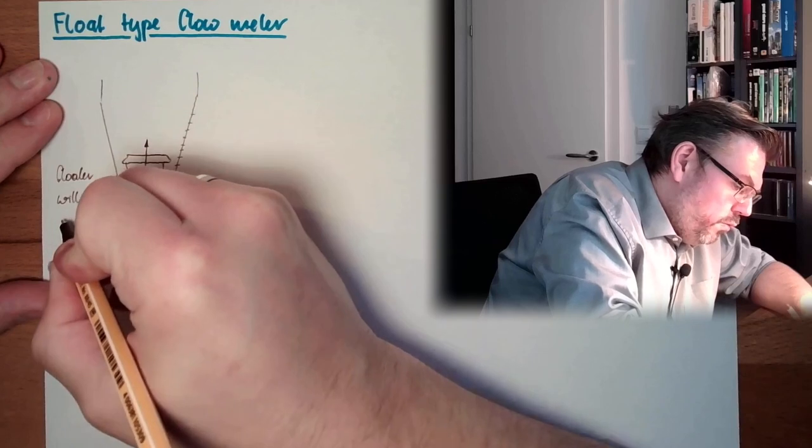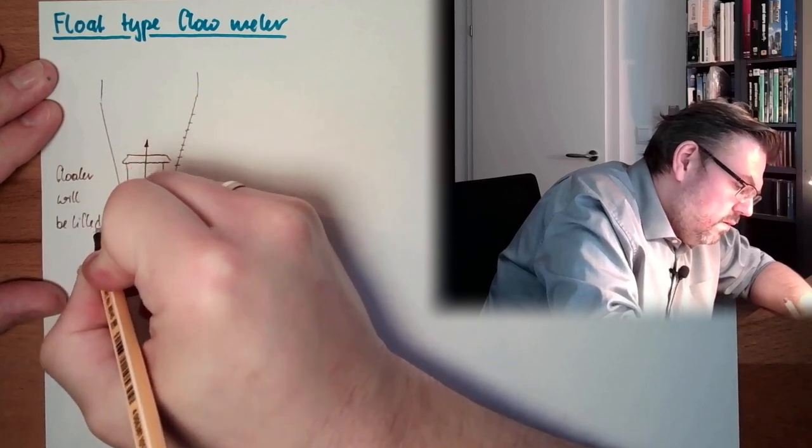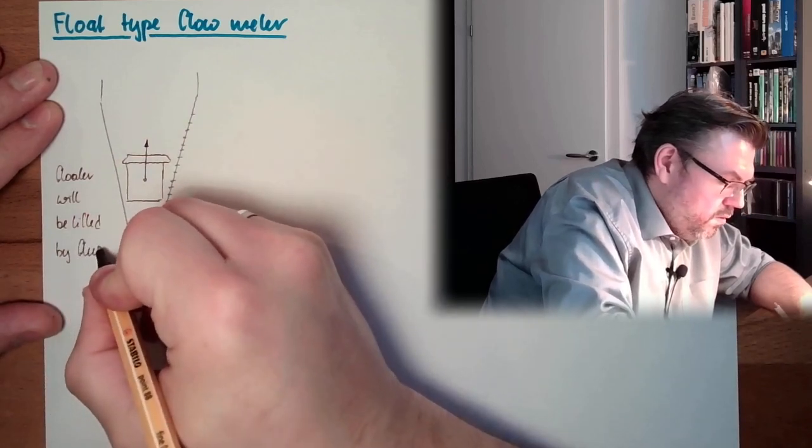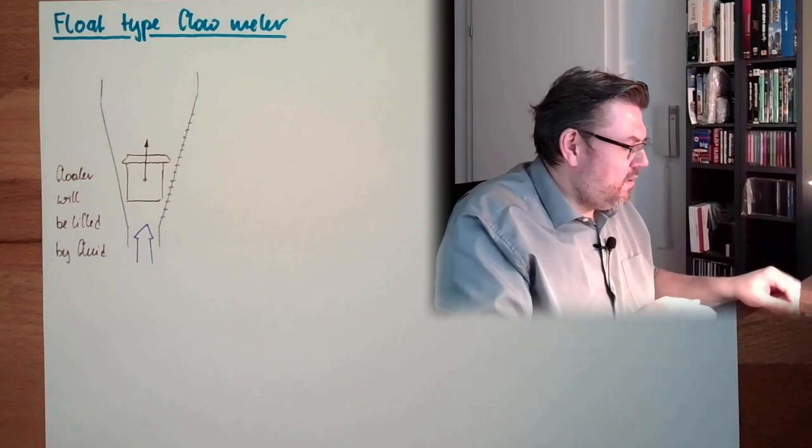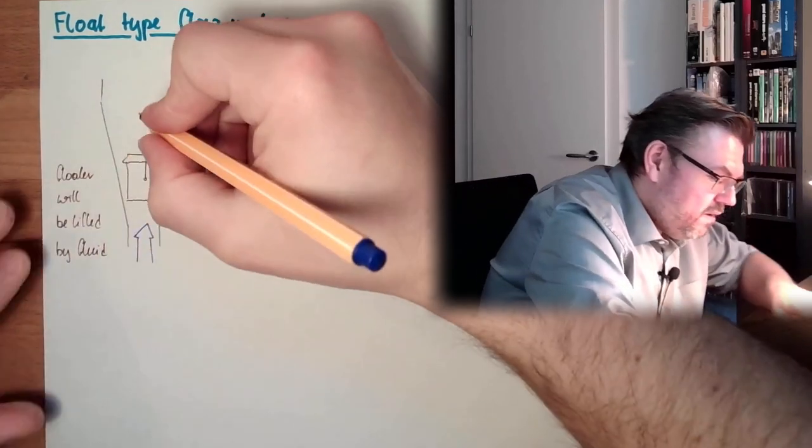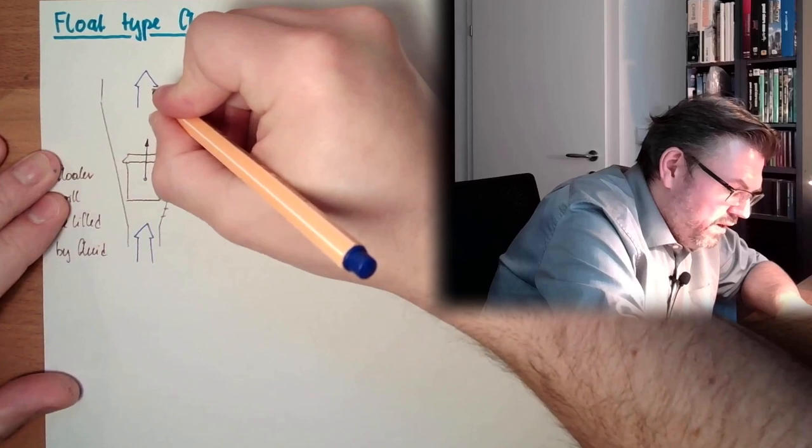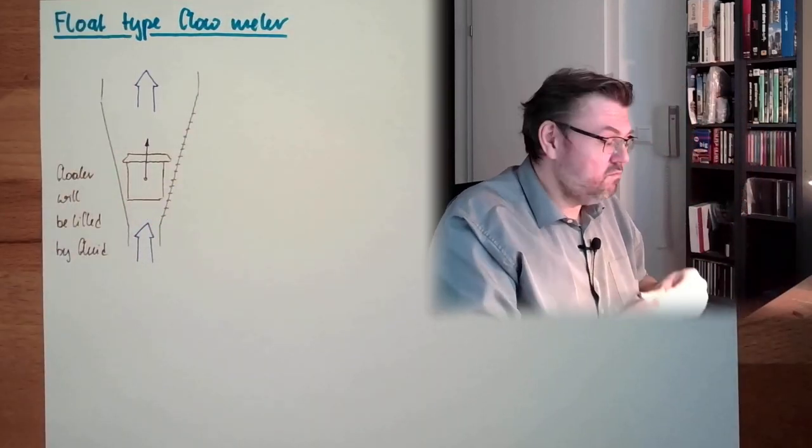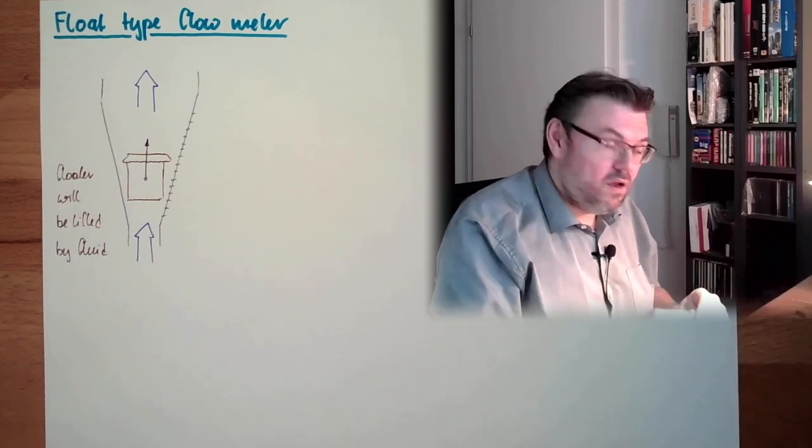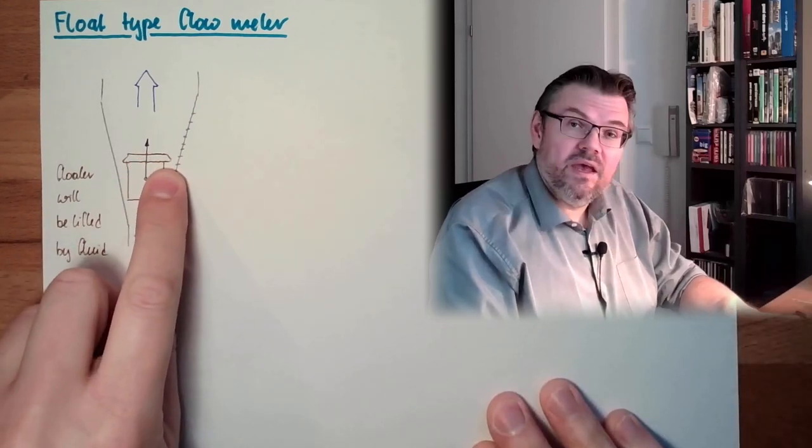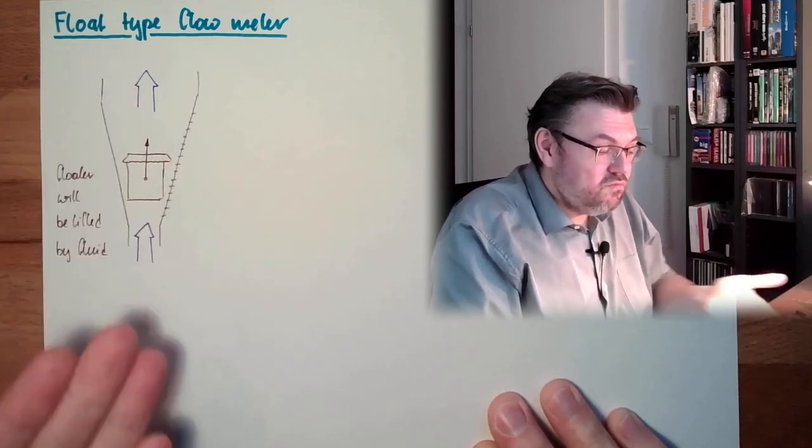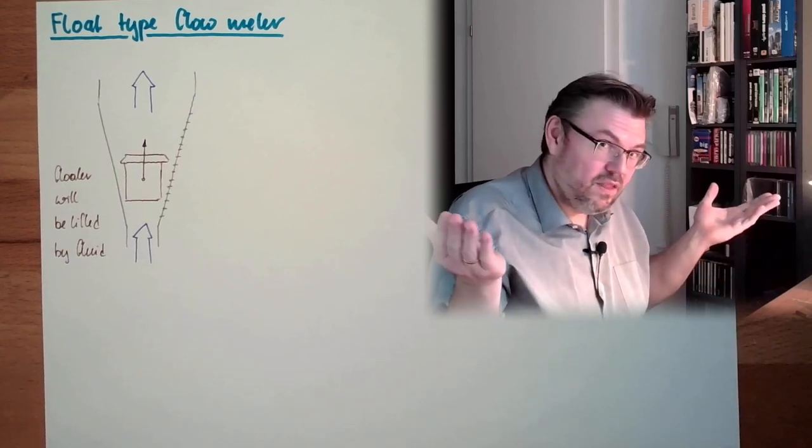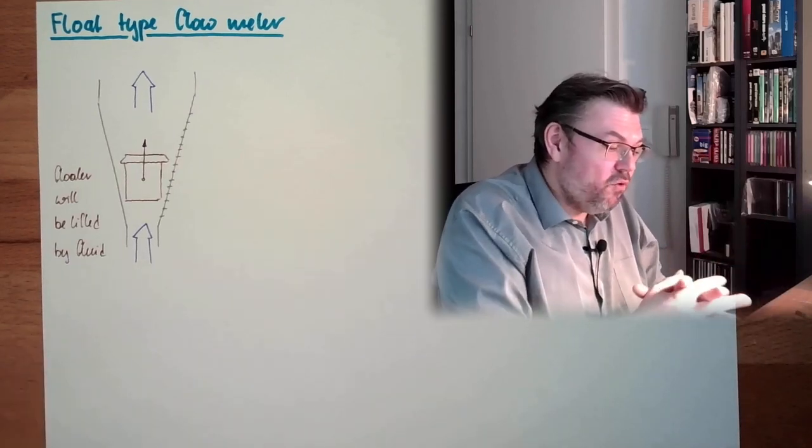The floater will be lifted, and here on the side, the fluid will then go on wherever it is needed. So it will simply pass through and will lift this floating element to a certain height. And if I can read the height at the scale, I know how much of this fluid is passing by. That's it. This is float type measurement.